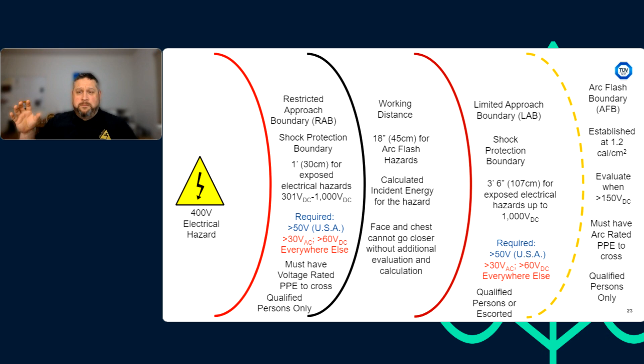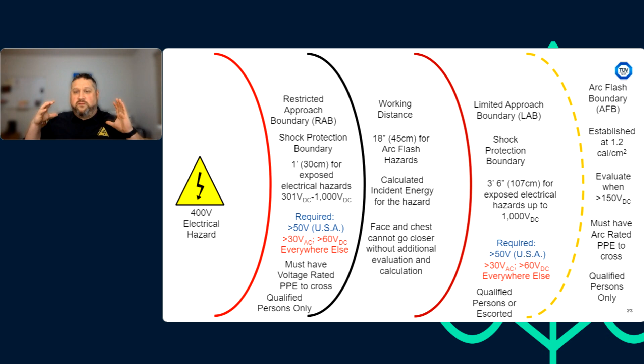So that would typically mean we'd have to have coveralls, leather boots, and our rubber gloves with leather protectors would protect our hands sufficiently. And then for our face, we'd have to have a balaclava, which is a sock hood that covers our whole face and back of our head, and then an arc flash face shield, as well as safety glasses underneath, and hearing protection as well. So there's a ton of PPE we'd have to make sure we have on to cross this boundary in order to keep us safe in case something went wrong.